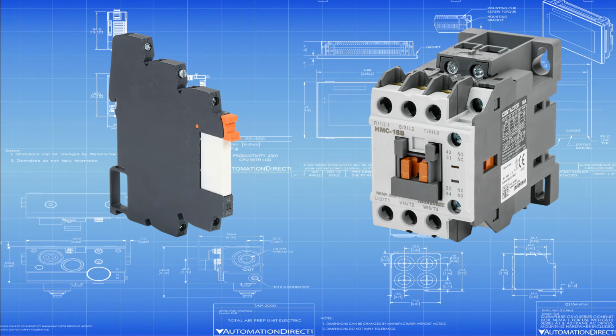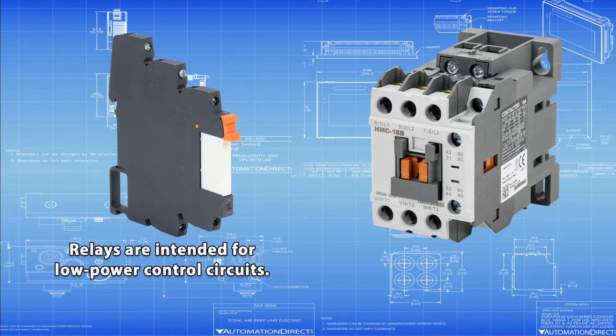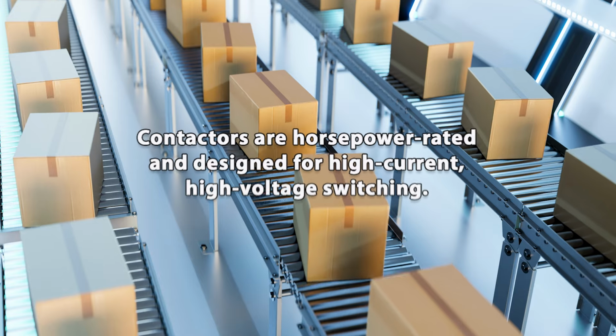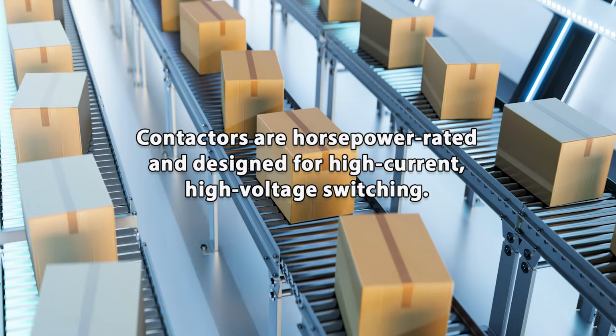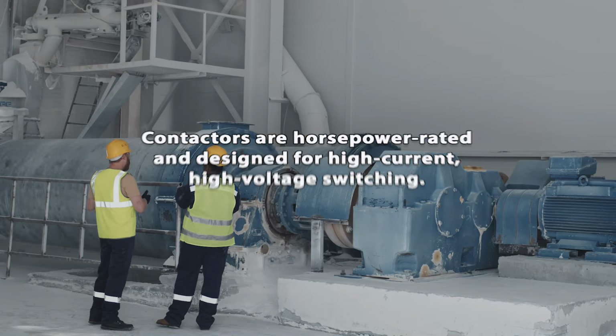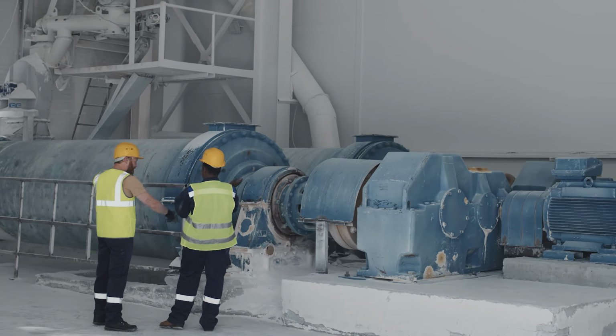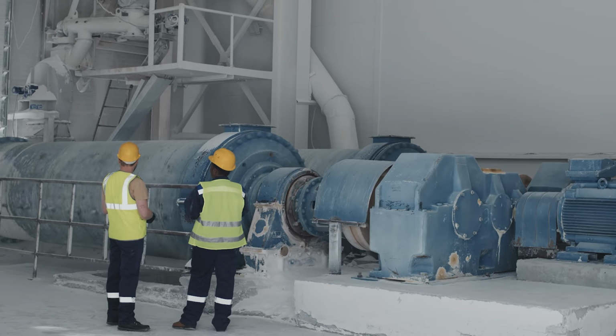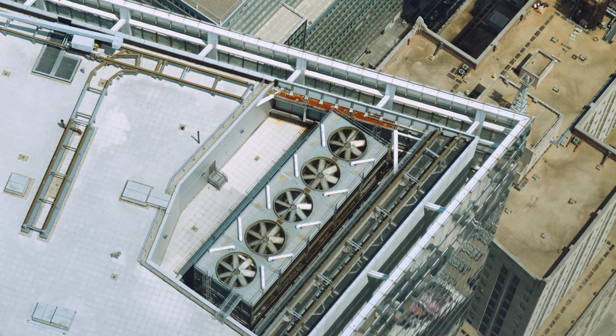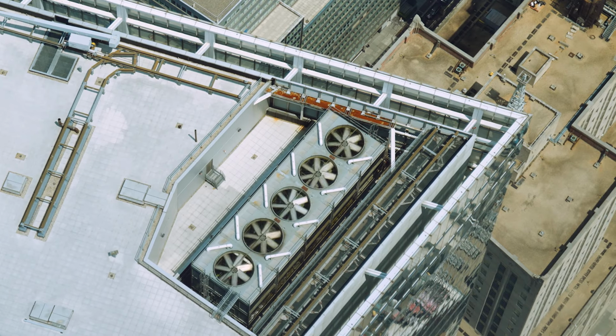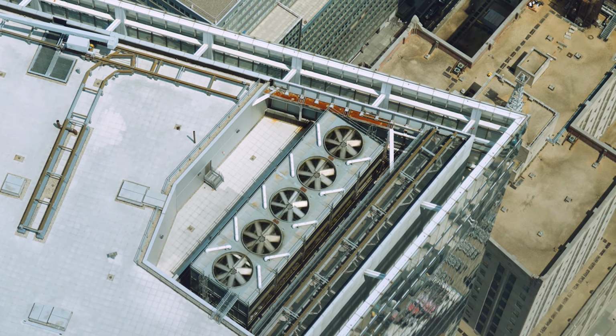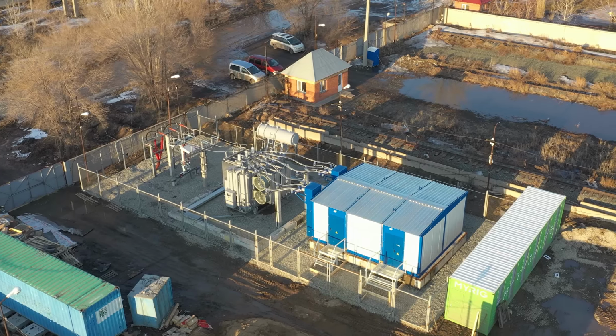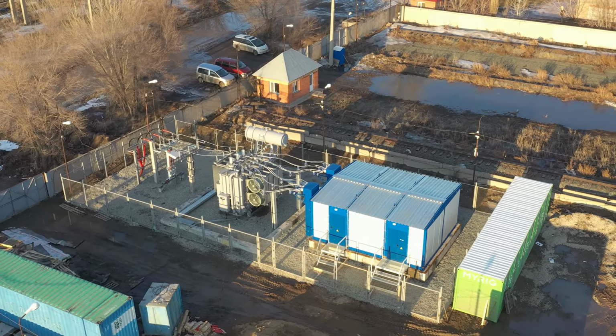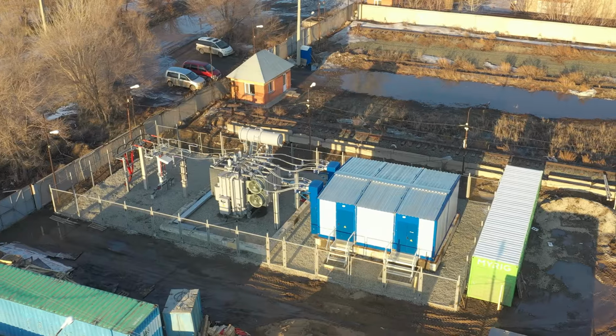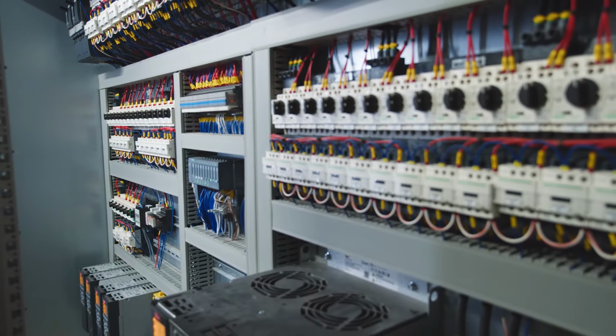Relays and contactors share the same electromagnetic principle, but relays are intended for low power control circuits. Contactors, on the other hand, are horsepower rated and designed for high current, high voltage switching, making them the correct choice for motors and other large loads. Some are even designed to allow easy assembly with additional components that monitor motor health or enable safe direction control. So whether you're starting a large motor or controlling industrial heating elements, the contactor is the reliable interface between your control system and high-power equipment.